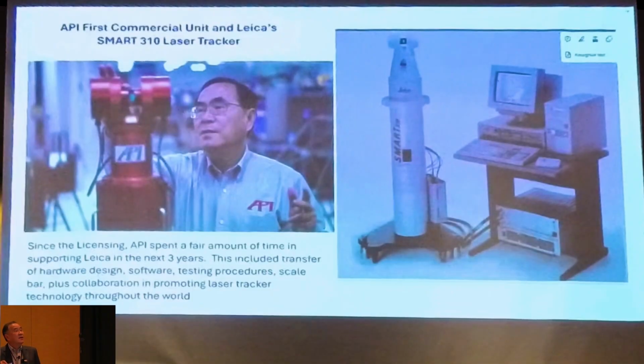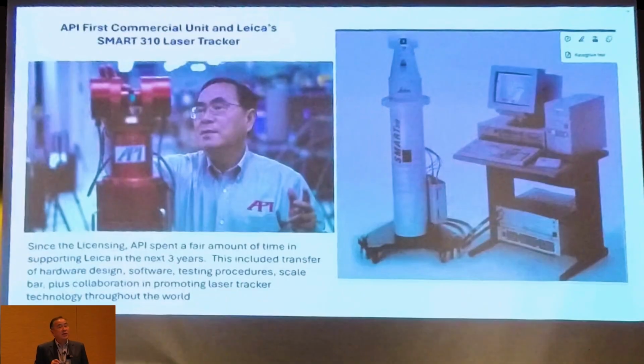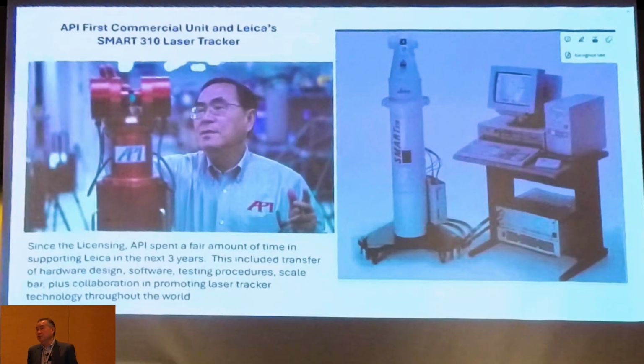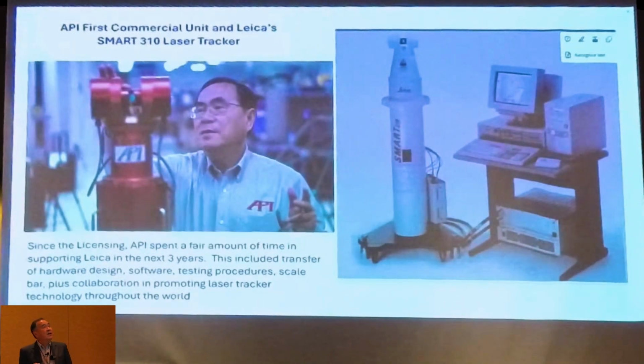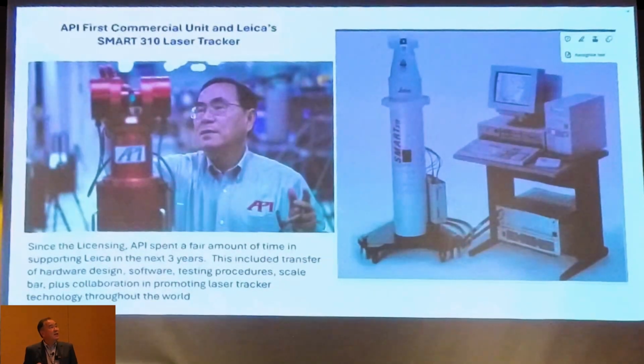So after the licensing, I spent around 3 years' time to support Leica to build a laser tracking system. I passed all the hardware, design, software, plus the methods of calibration of laser tracking system to Leica. At the same time, I helped them to promote the tracking technology throughout the world. If you look at the earlier model, the API laser tracker is what we call generation 1. The laser in the front is underneath, shooting through the gimbal. This is a 2-axis gimbal, AZ axis and EL axis, and there's a mirror there. So the laser goes through the gimbal into the mirror and shoots out, pointing to the target.